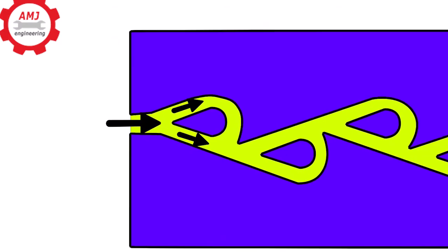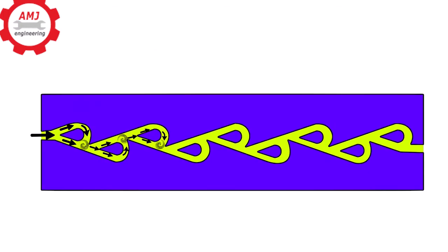On the other side, secondary flow loses velocity as it reaches the bucket at the end of the flow control segment. Secondary flow is reversed almost 180 degrees and pushed back into the path of the primary flow, but in the opposite direction. Vortices and turbulence are formed where the secondary flow rejoins the primary flow, further restricting progress. This happens again at every control segment, restricting the flow again and again.